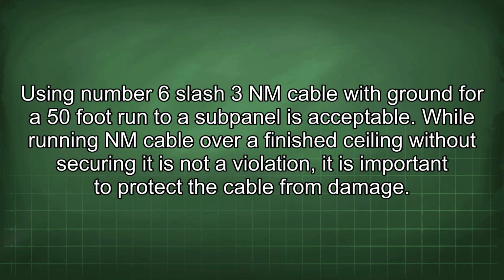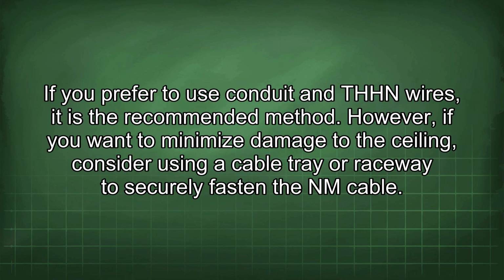Using number 6/3 NM cable with ground for a 50-foot run to a subpanel is acceptable. While running NM cable over a finished ceiling without securing it is not a violation, it is important to protect the cable from damage. If you prefer to use conduit and THHN wires, it is the recommended method. However, if you want to minimize damage to the ceiling, consider using a cable tray or raceway to securely fasten the NM cable.